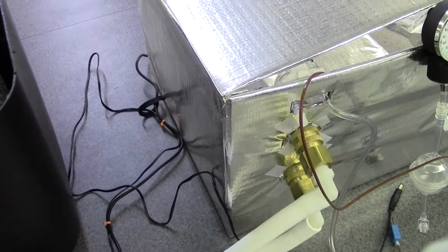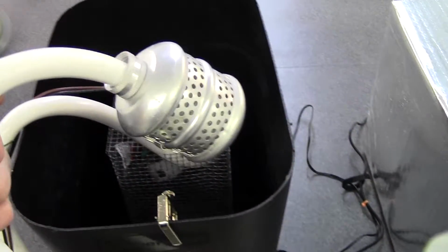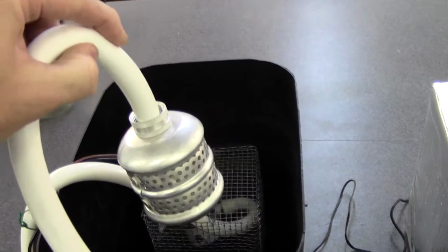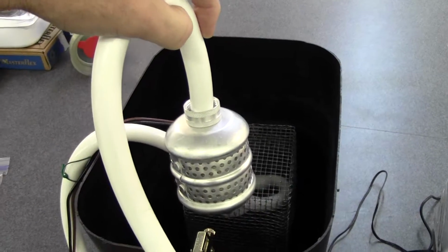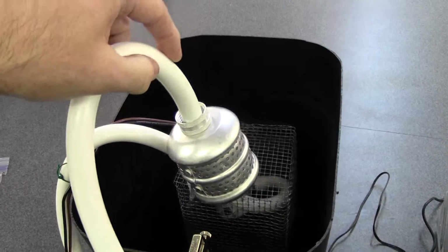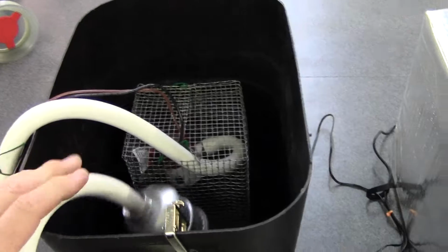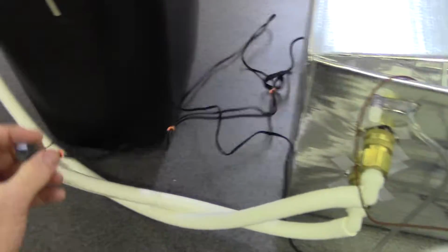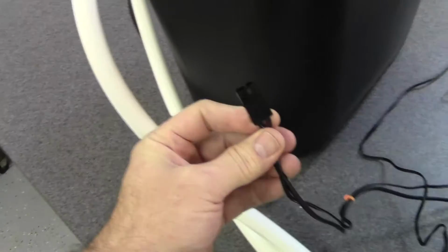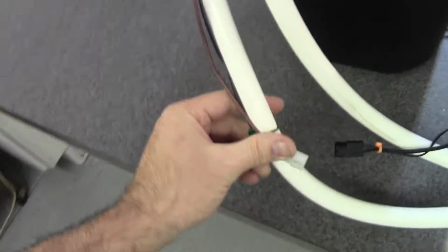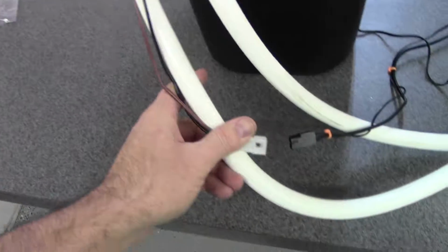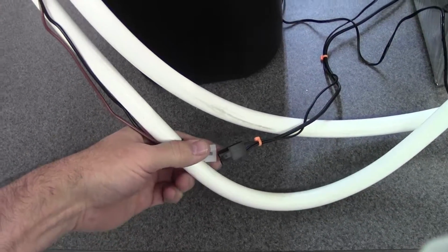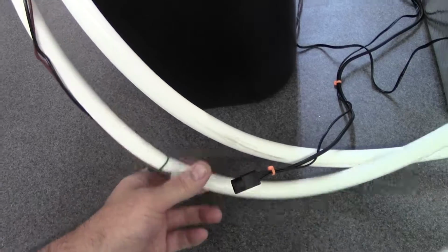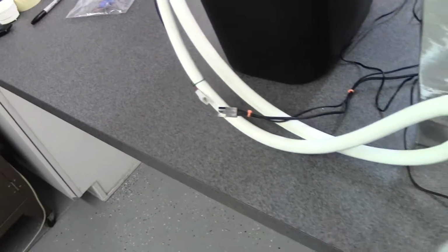Okay, let's see. So this is the return line here. You'll set this on top of the ice and try to get it sitting nice and straight so that we get the most surface area of ice flowing with return water ethylene glycol. And our little power supply has a plug. It's keyed, it only goes one way, and here is the power to the pump. So those two plug in together, and that'll do that.